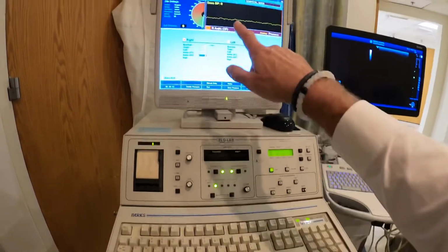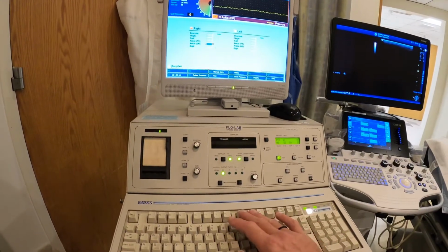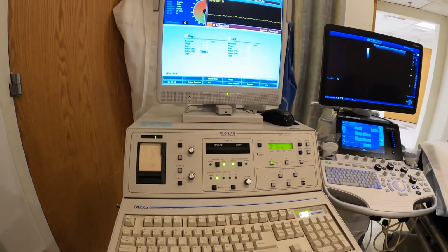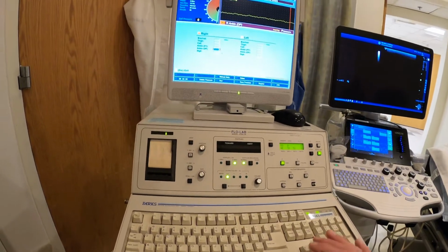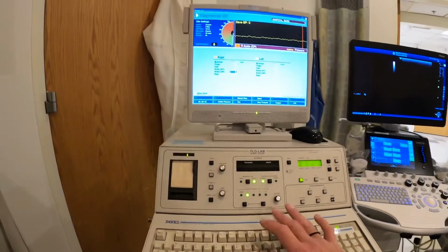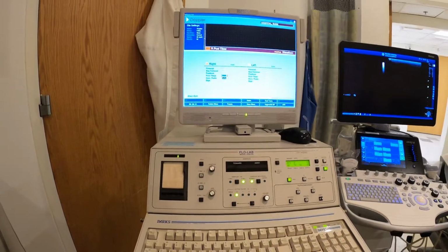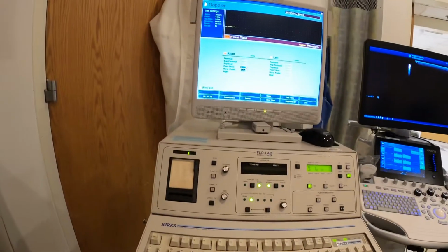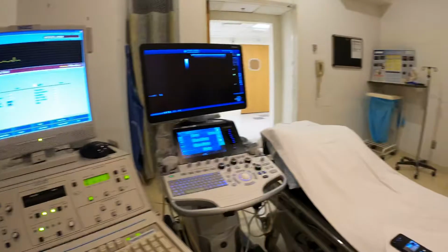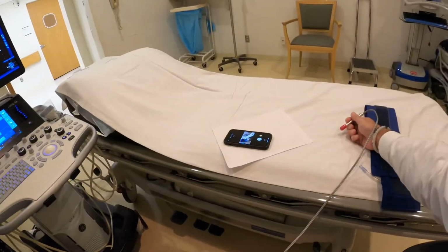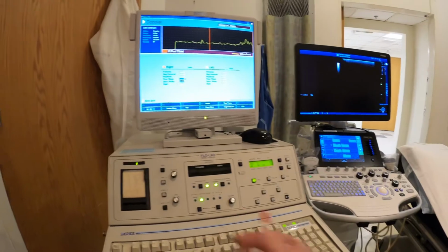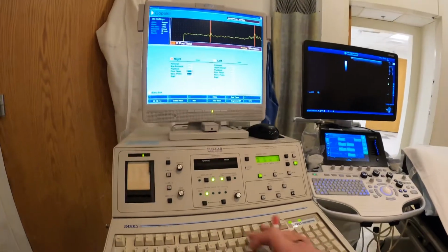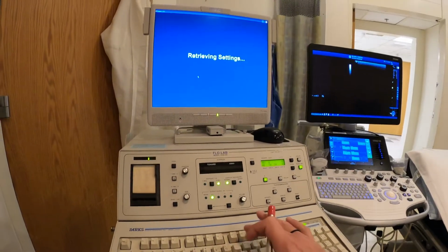That saves the blood pressure, at the point you hear the first signal. If you don't like it, you can back it up a little bit and obtain the proper pressure. Hit F10 to save it. The machine automatically goes to the right posterior tibial. Obtain that Doppler signal. Right posterior tib. F9 to stop it. You like it, you don't like it. Go back a couple. Save it. F10.